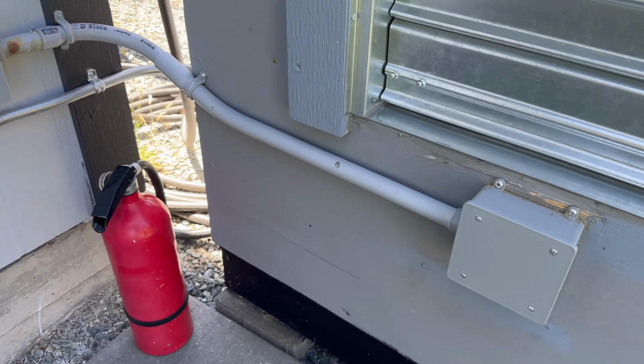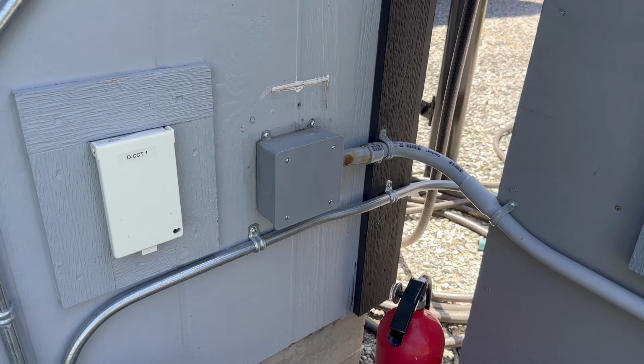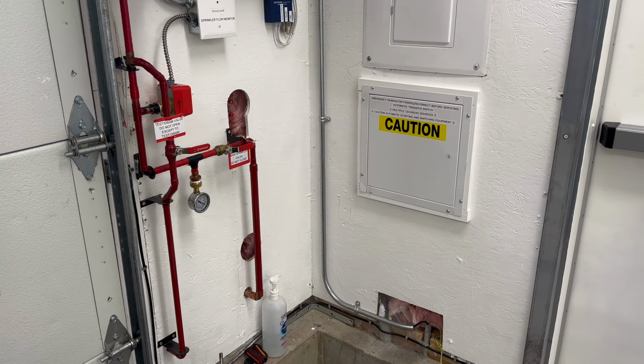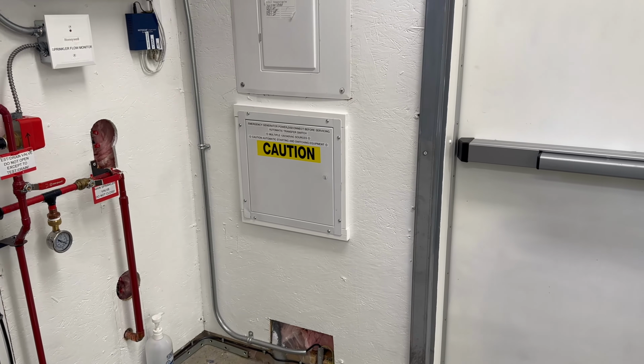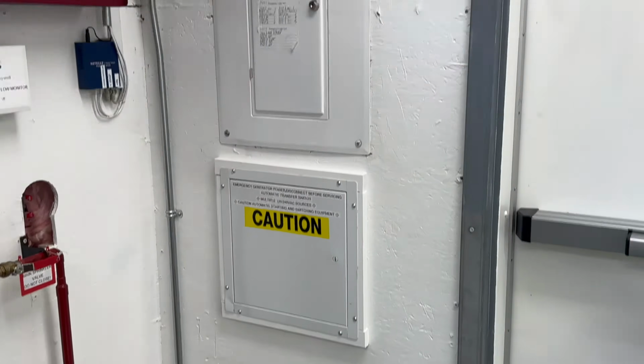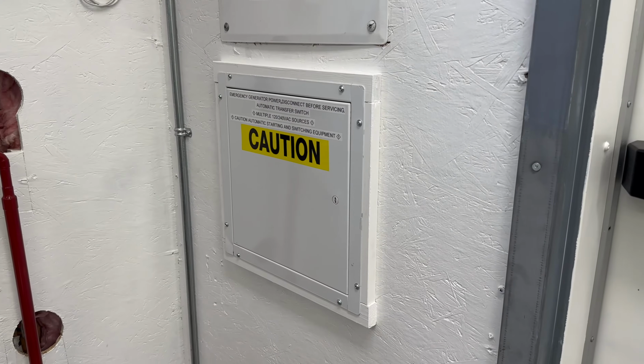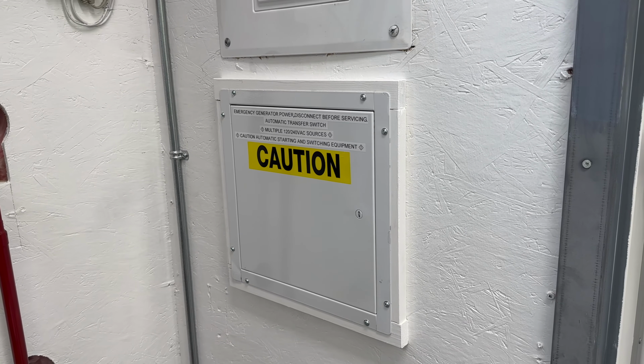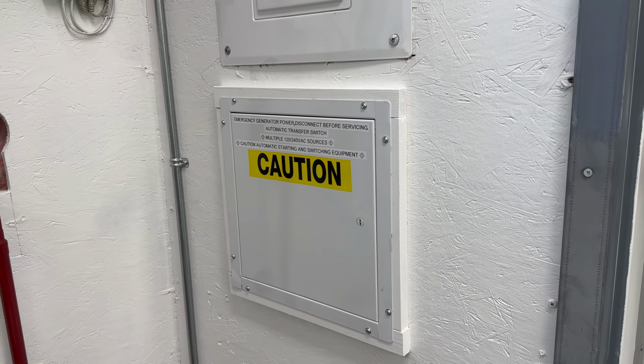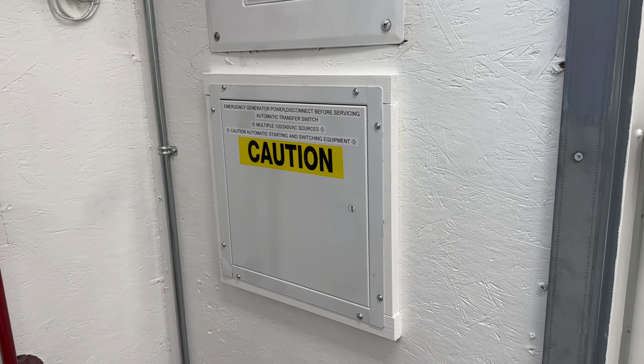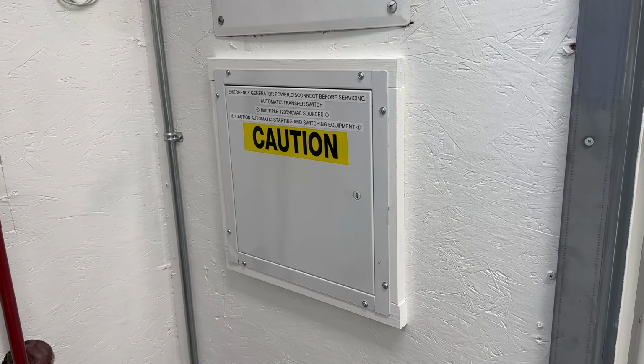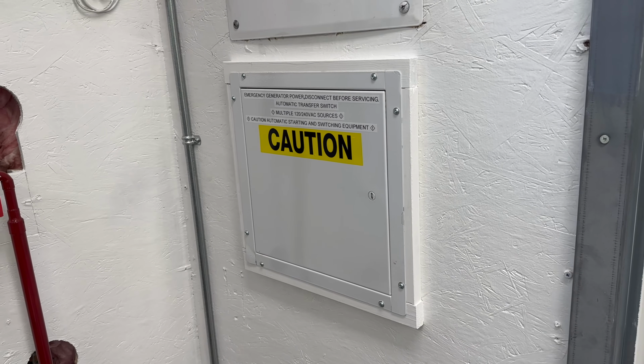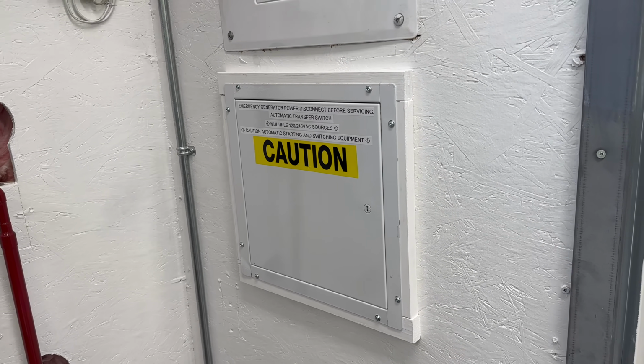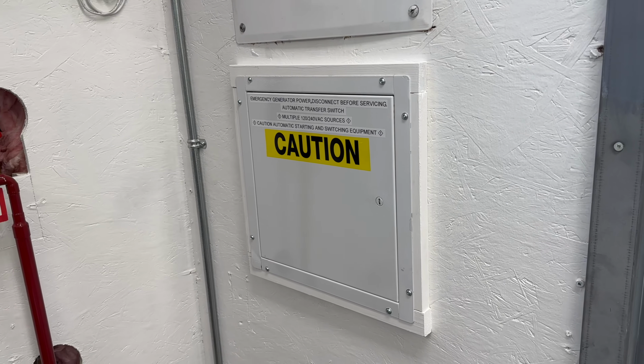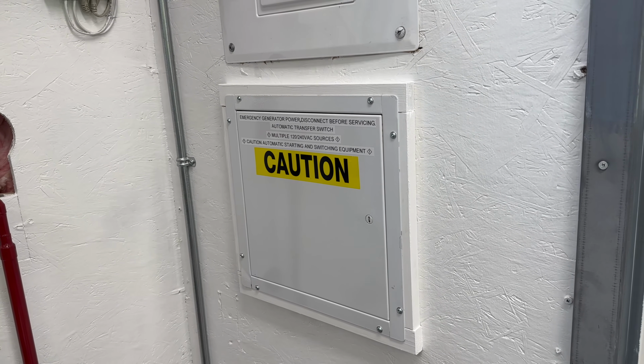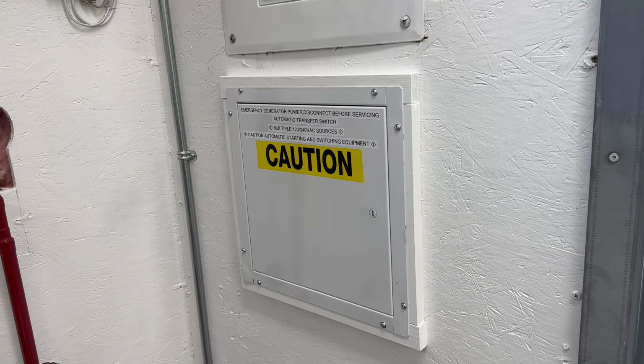After that point, they run through this box and through this conduit into the side of the main garage building right there. And they go into this wall right here, into this box, which is mounted just below the electrical panel. Mounted in here is what is known as an automatic transfer switch, which is a set of contactors that will switch between different power sources. In my case, the two different power sources are regular power and our emergency power. The regular power being provided by BC Hydro, and the generator power is coming off of the generator, which is only on when the power is out.